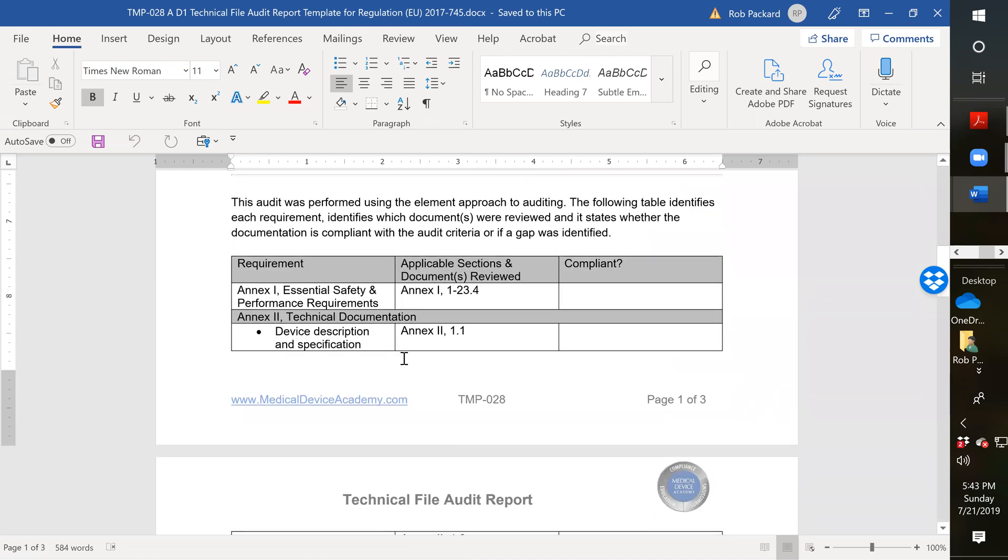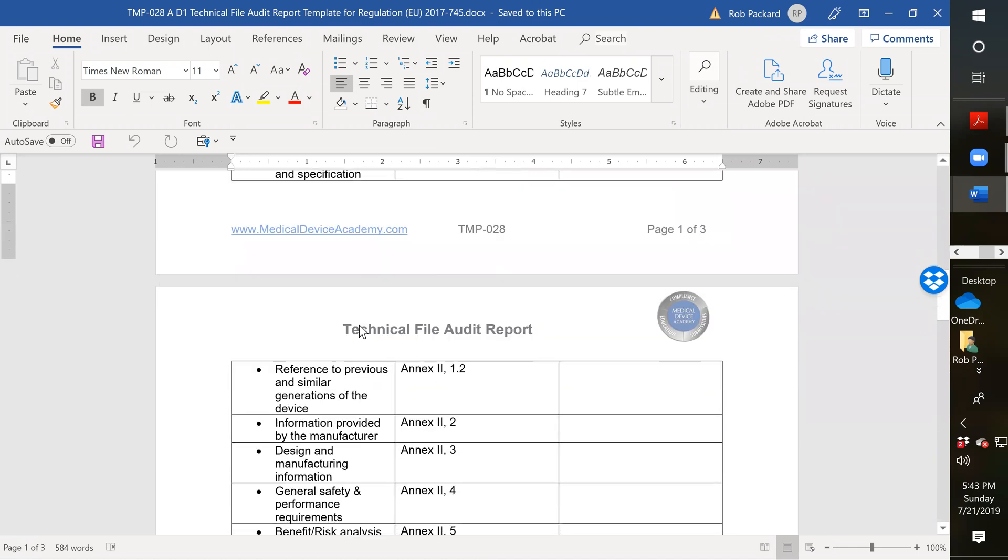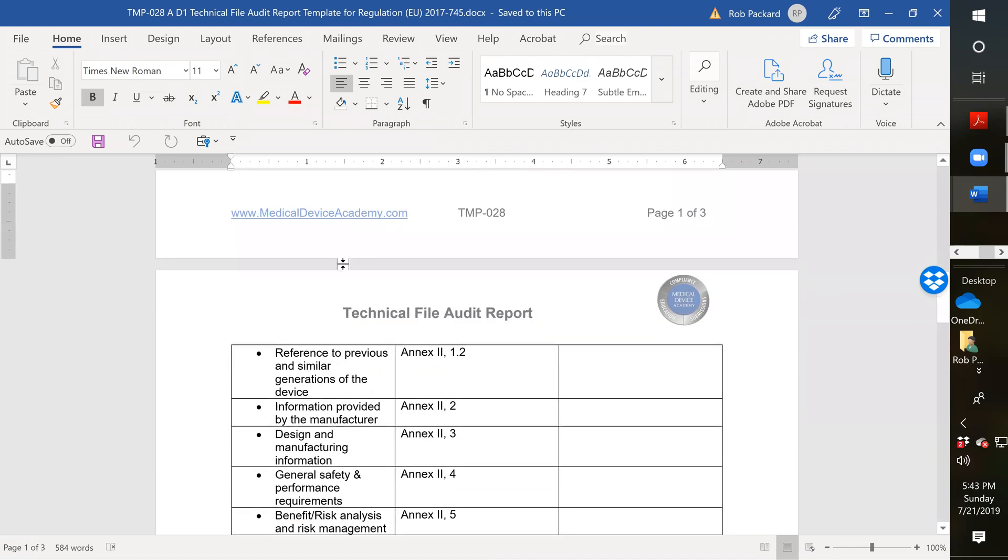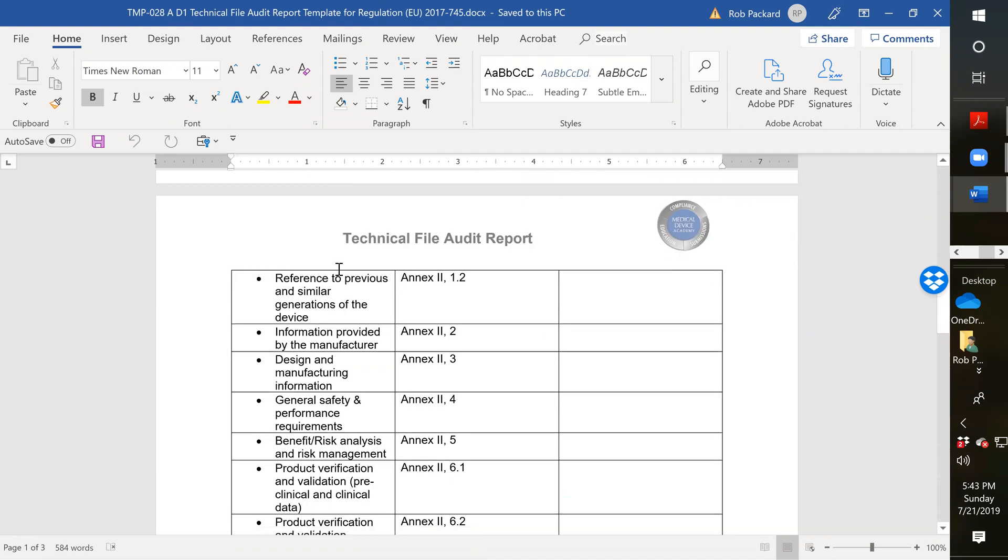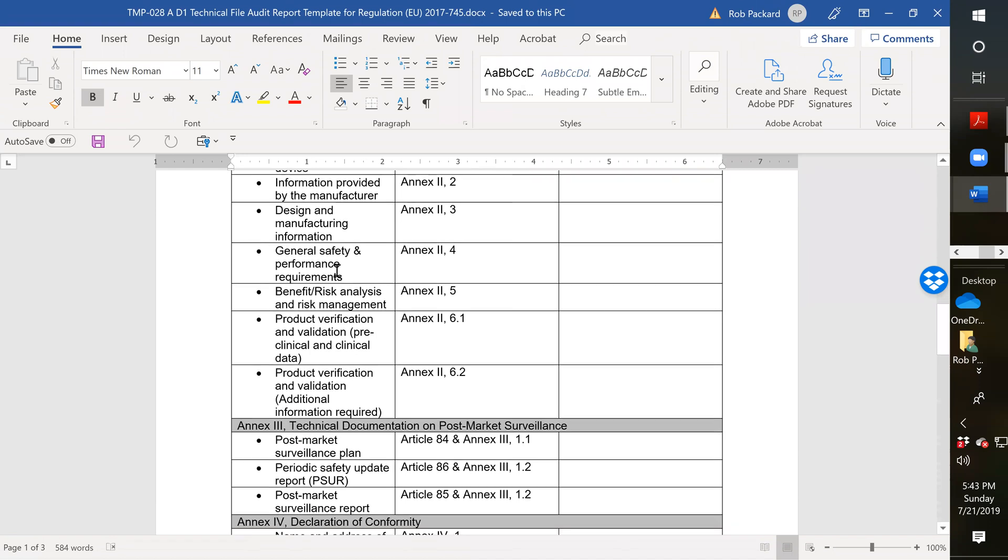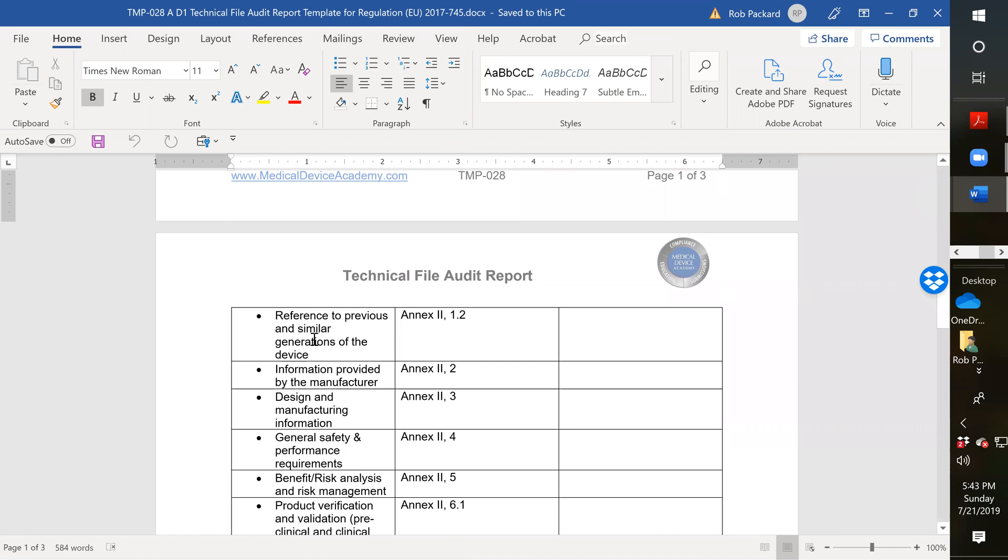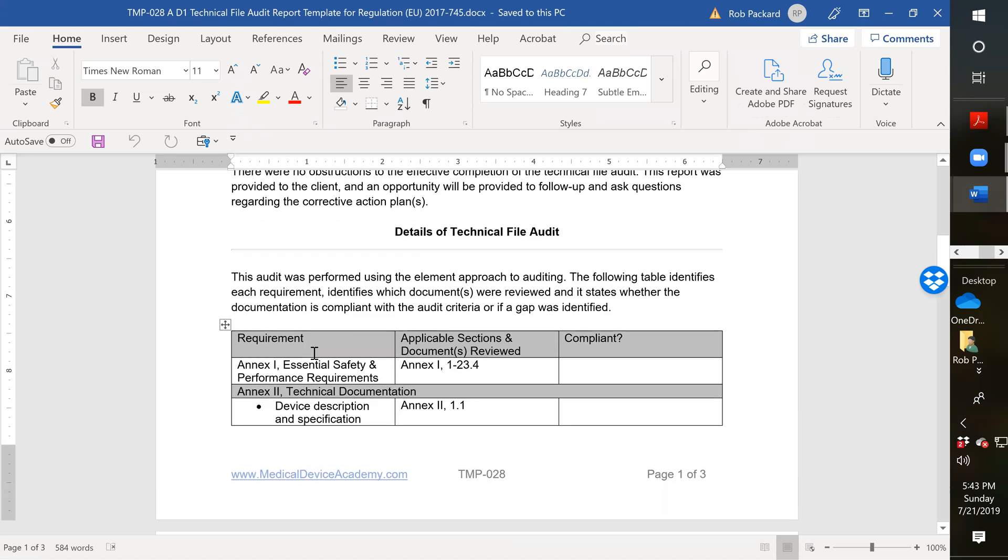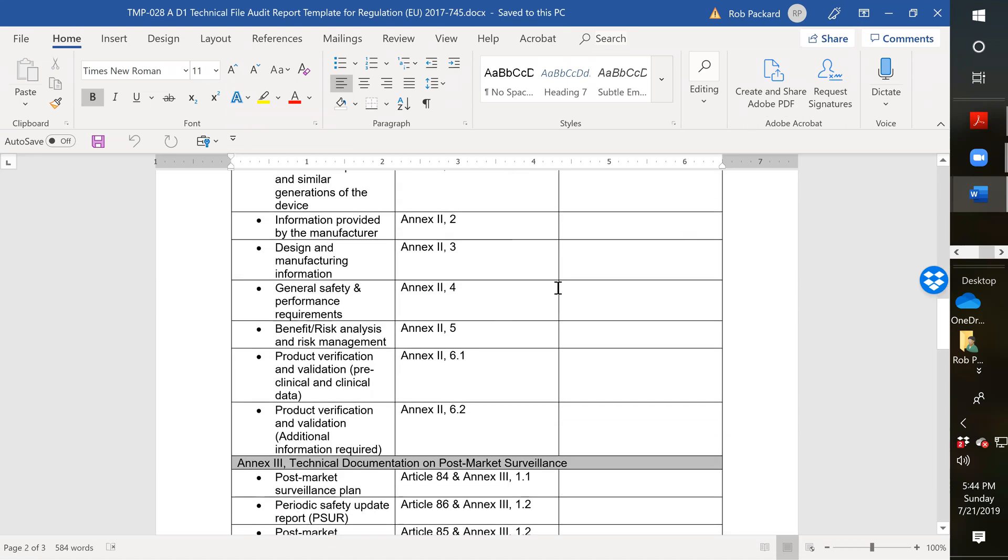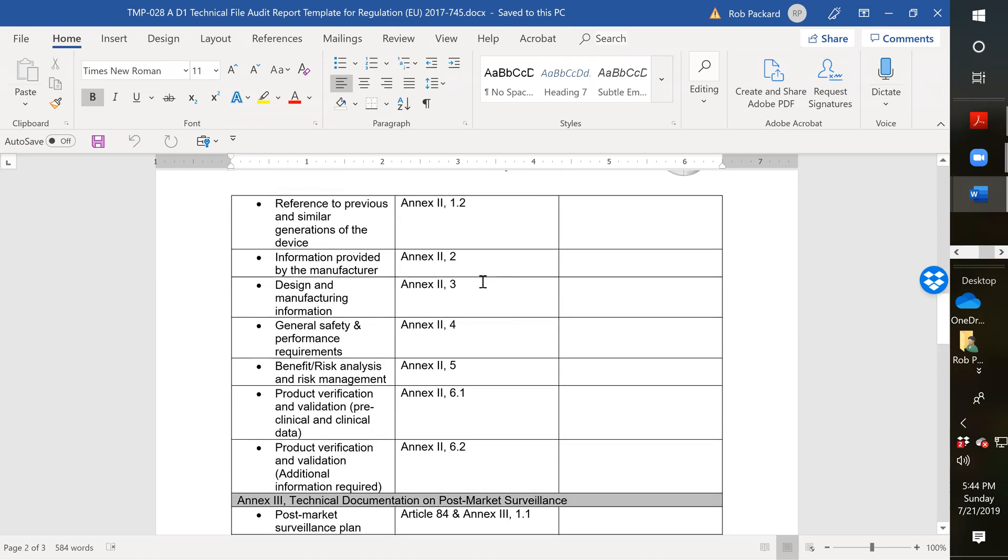The next section that we look at is Annex 2, and this is the technical documentation. Most of this should be very similar to what they have had before. We always had to have a device description, previous and similar generations of the device, information provided by the manufacturer which is the labeling section and instruction for use, brochures, things like that. The design and manufacturing information is where we would provide drawing specifications, flowcharts, the manufacturing process flow, manufacturing procedures. This is a cross-reference to the Annex 1 essential performance requirements.